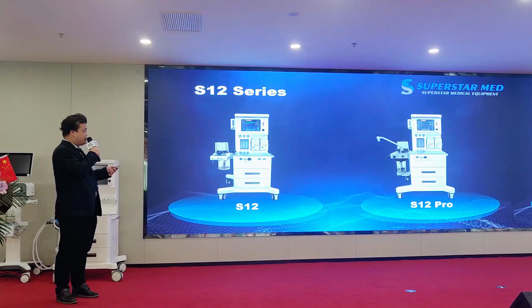Okay, as you can see for our new model, the main difference from before is the appearance. You can see it has become a little bit slim. Why did we make it this way? Because in clinics nowadays, in different theaters or operation rooms, the space is limited, especially in small hospitals and clinics. So this appearance saves space. At the same time, in an anesthesia system, the gas comes in from the back of the machine and finally goes to the mask and to the patient for breathing, which is a very long route. If we make the anesthesia machine more compact and slim, the route will be shorter and the loss will be less. Then the patient can get all of the data, with no leakage. So this is why we have this design.